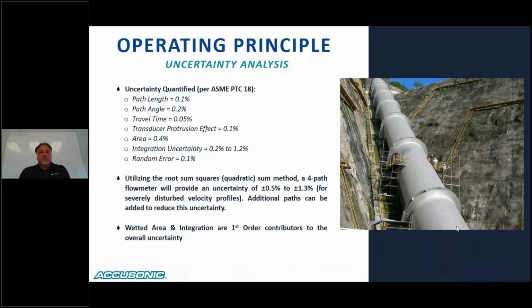The uncertainty analysis, once we get into it, is quantifiable. They do recommend doing it for contractual turbine testing and stuff like that for ASME PTC 18. The quantifiable values here are path lengths, path angles, travel times, transducer protrusions, the wetted area, the integration uncertainty, and the random error. Those all get summed together utilizing the root sum squares method, and we're typically in the plus or minus 0.5% range.